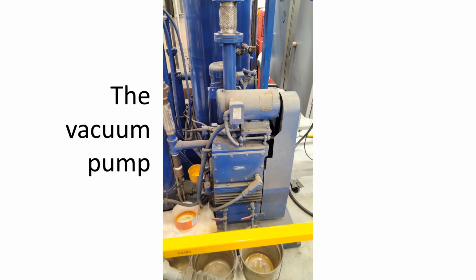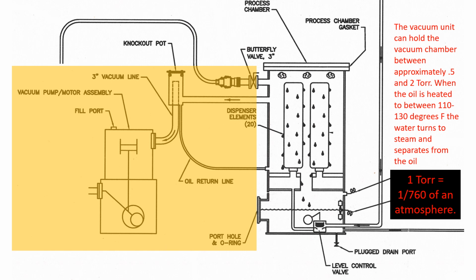If you said a vacuum pump, you're correct. When water is introduced to a vacuum, it turns to steam at a much lower temperature than the normal boiling point of water, which is 212 degrees Fahrenheit. The vacuum unit can hold the vacuum chamber between approximately 0.5 and 2 torrs. When the oil is heated to between 110 to 130 degrees Fahrenheit, the water turns to steam inside the vacuum chamber and separates from the oil. 1 torr is equal to about 1/760th of an atmosphere.